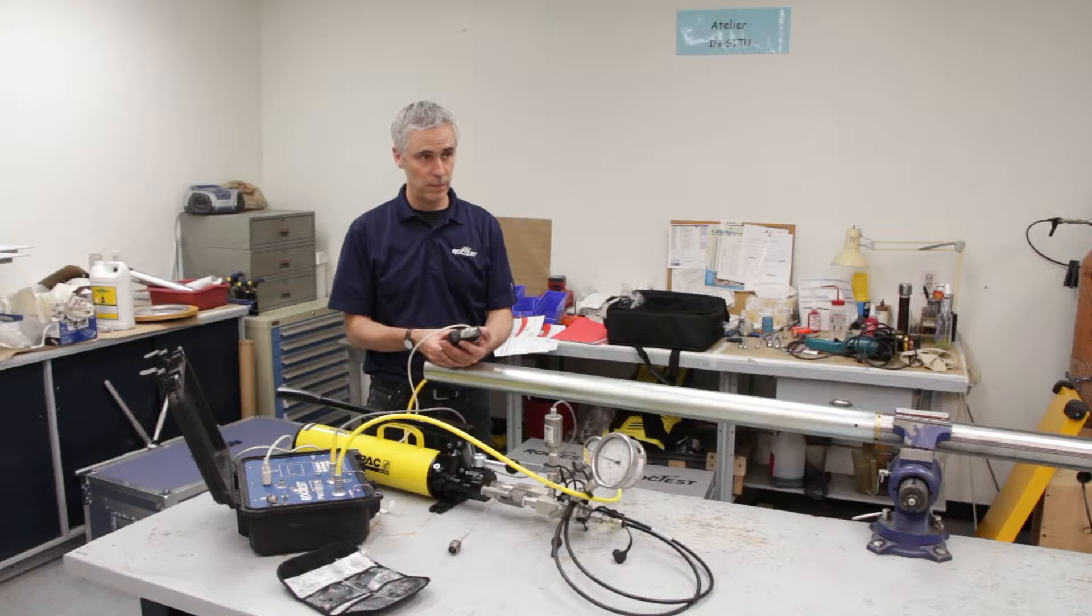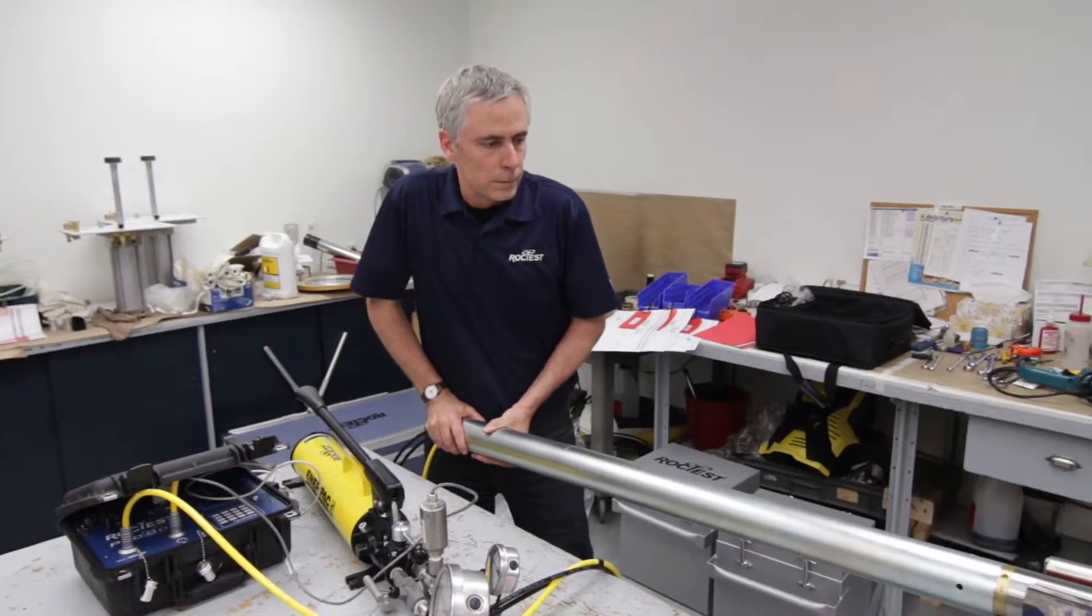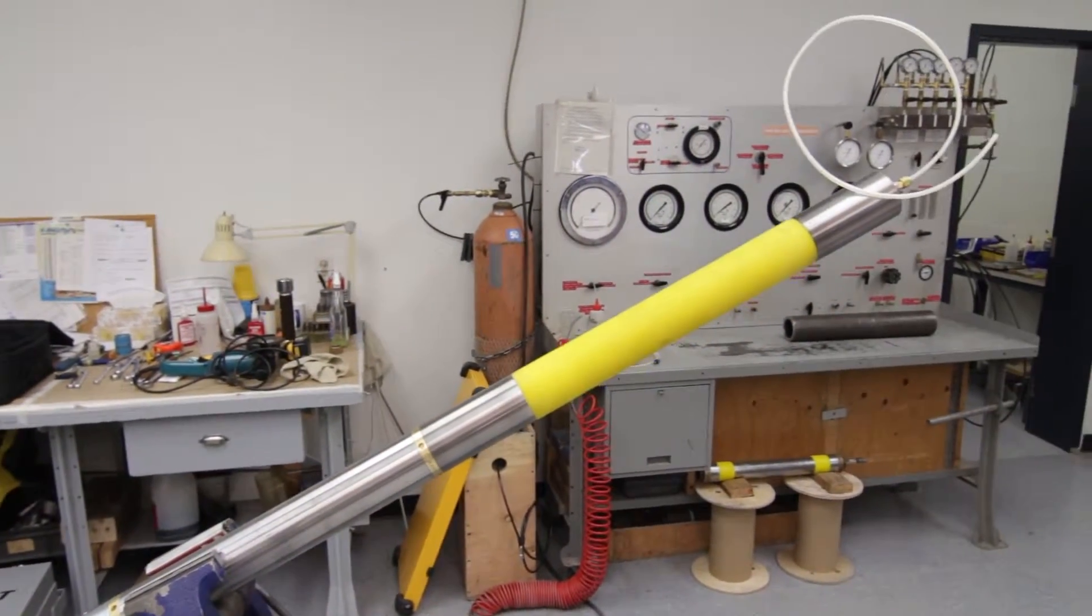You should also see a jump in your pressure reading. Incline the Probex by a minimum of 20 degrees while making sure the saturation plug is at the uppermost point.